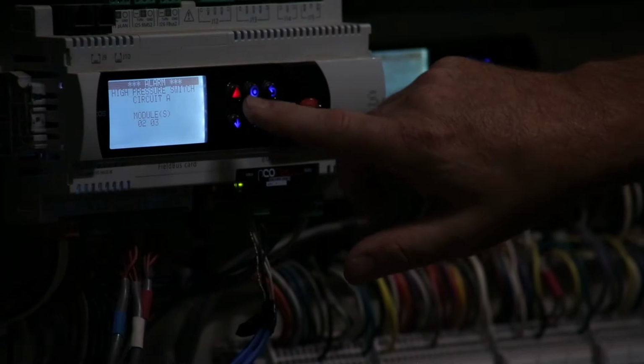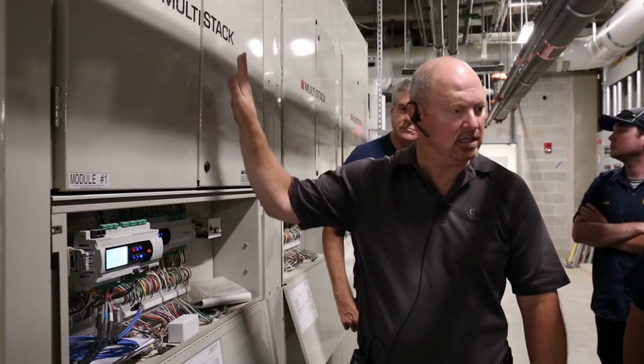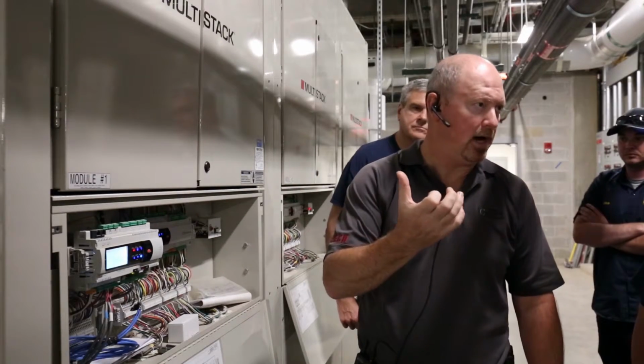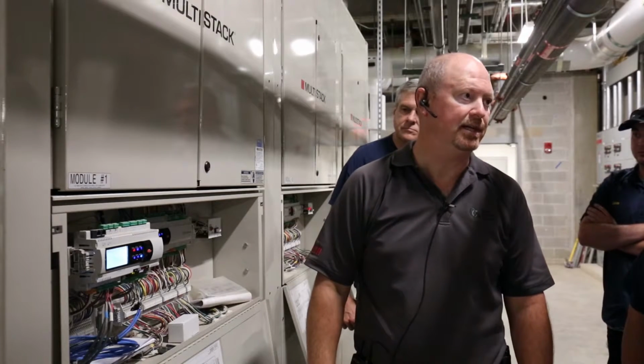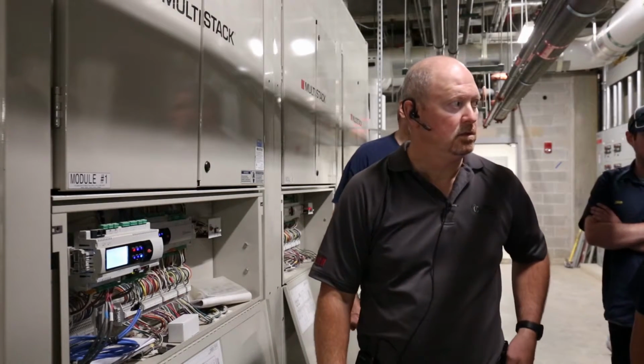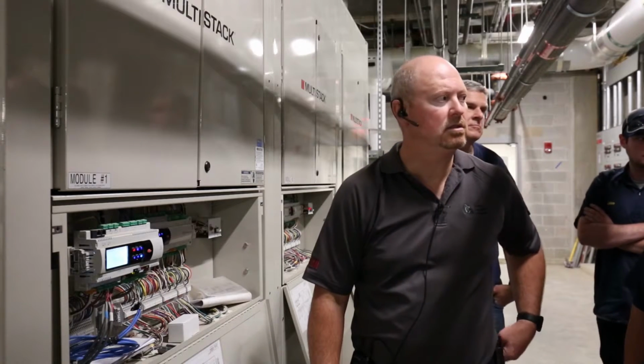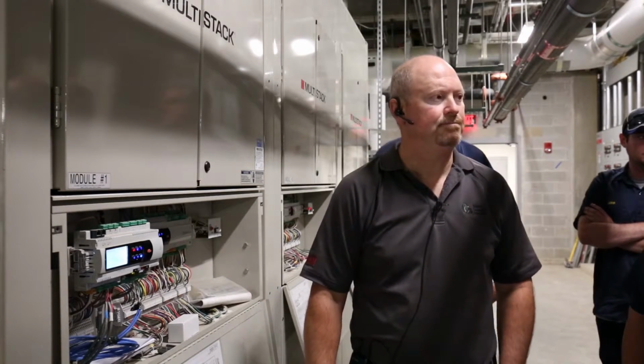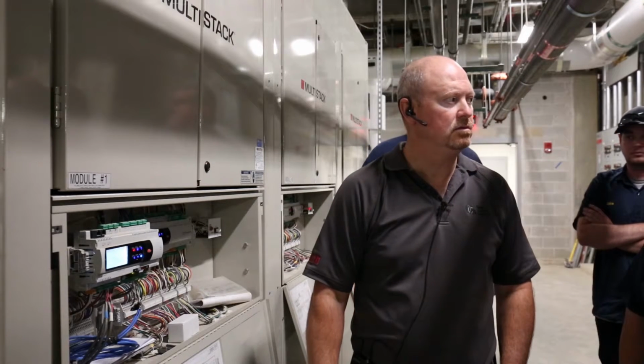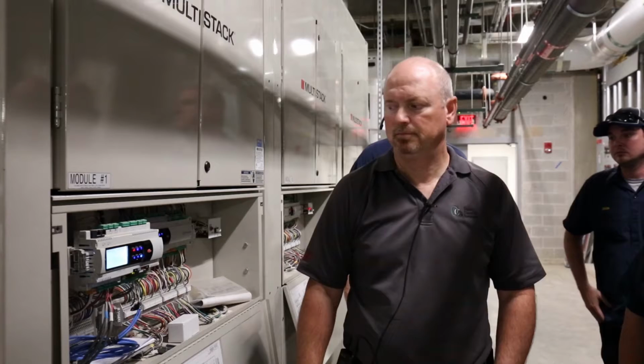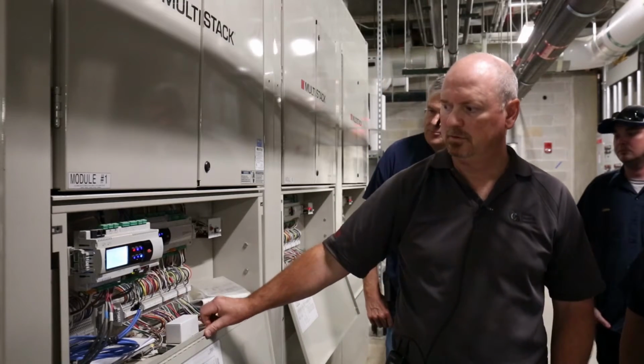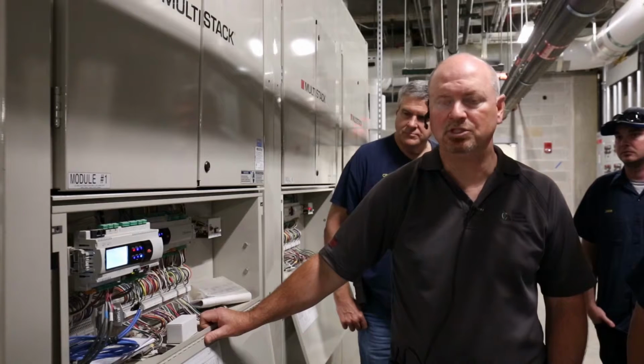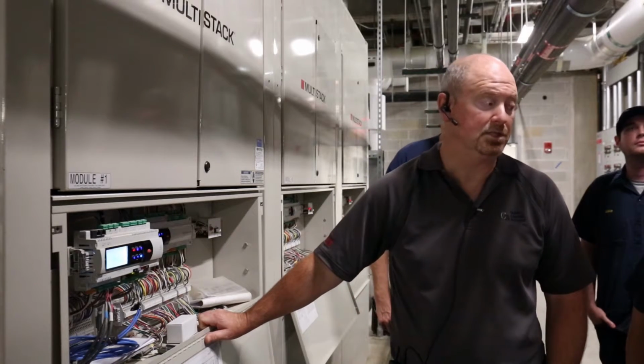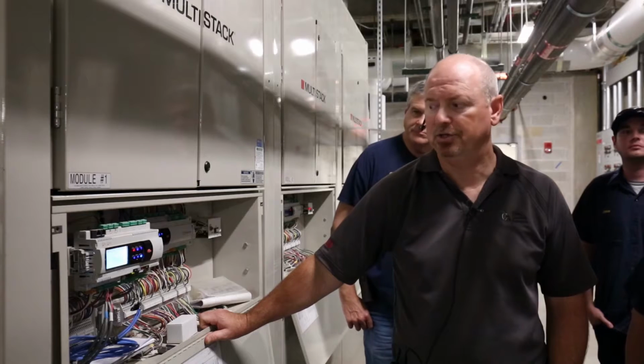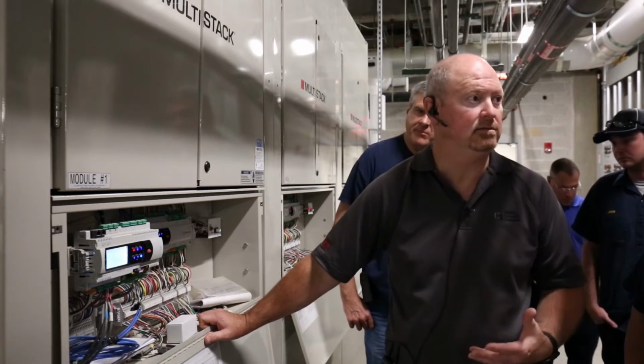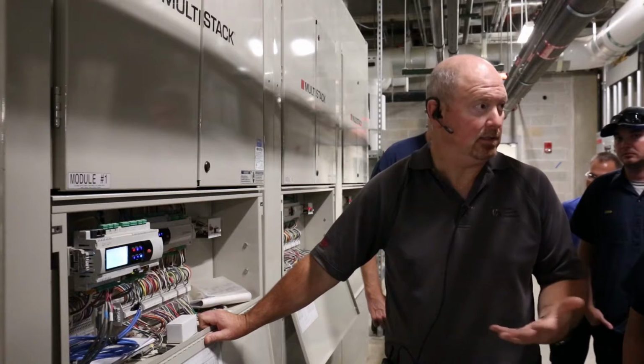Your high pressure switch is inside the module here, and you have to push a button to reset it. So with your point, it's probably a flow. Yes, the sequence probably isn't quite worked out yet, so it probably lost flow, which caused it to go off on high head. It won't flow because we're not running the condenser water pump. Right. Most of the problems that you have with most chillers is water flow. And you just need to know how to get in and reset, once your problem's corrected, obviously.